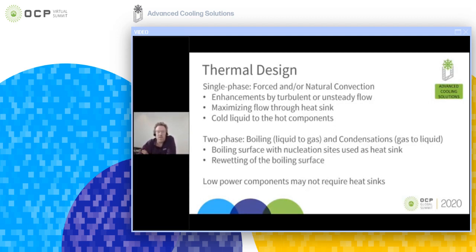The boiling enhancement coating introduces and enhances the number of nucleation sites, where the phase change is first initiated and bubbles are being formed. It's not only the formation of bubbles that is of importance for enhanced heat transfer, but also the re-wetting of this boiling enhancement coating. The re-wetting makes sure that the liquid is there to replace the one that just changed phase into gas or a bubble. One of the advantages of immersion cooling is that the immersion liquids have better heat transfer properties than air and is therefore more efficient in removing the heat from the hot components. This allows for not needing heat sinks on low-powered components on the board.